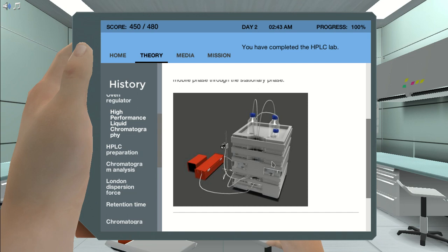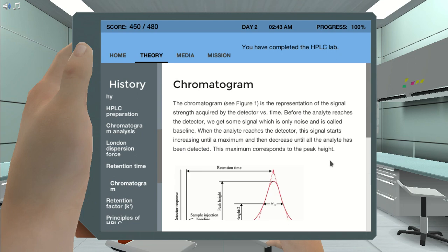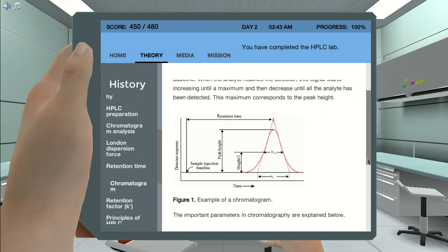This spectrophotometer does not require you to put a cuvette in there. Instead, it shoots its light at a transparent tube that is running through it. That tube contains your sample getting pushed through at high pressure. As time goes by, it just keeps on recording the absorbance, and that is where the chromatogram comes from. This peak is the absorbance of your sample as it gets pushed through. After it comes out of the column, it's all separated into its different components. The absorbance is high when something passes through the light in the detector, and there's no absorbance when it's just pure solvent passing through the detector. That is what is going on, just spectrophotometry.